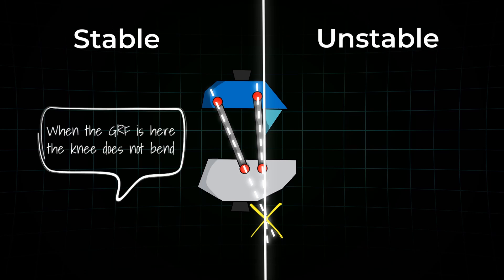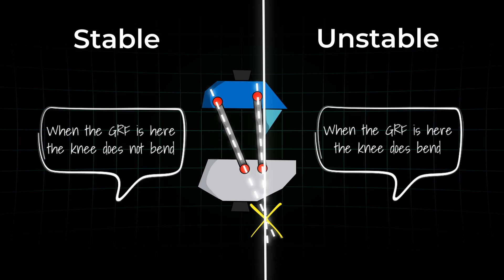But as soon as the ground reaction force moves forward, the knee flexes, allowing for a smooth transition into swing phase. These designs are kind of rare, but they can be extremely helpful for users who need maximum confidence during standing or walking.